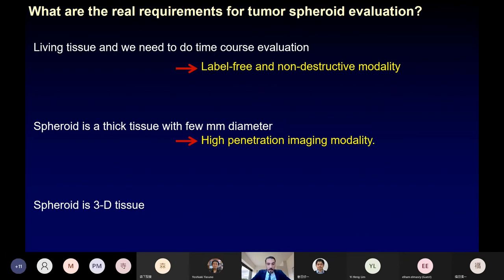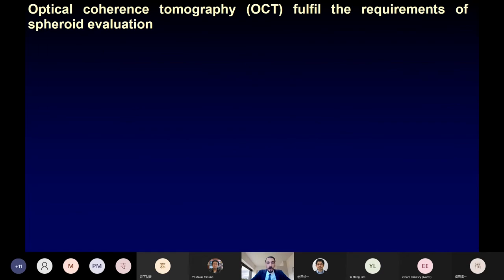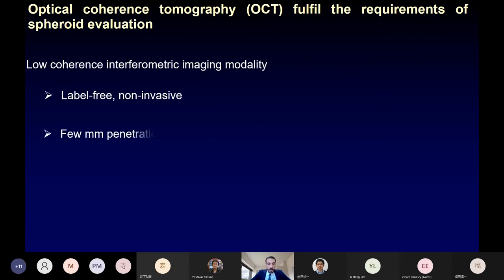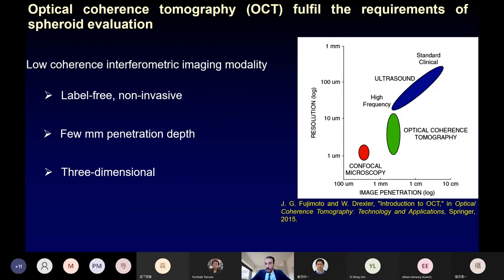All of these requirements are satisfied in optical coherence tomography (OCT), which is a low-coherence interferometric imaging modality providing label-free imaging with a few millimeter penetration depth, and it is three-dimensional. OCT fills the gap between conventional ultrasound and confocal microscopy. Ultrasound provides a few centimeter imaging penetration but with low resolution, while confocal microscopy provides a few hundred micrometer penetration depth with high resolution around one micrometer. OCT stands in between, providing a few millimeter penetration depth with relatively high resolution of around 10 micrometers.